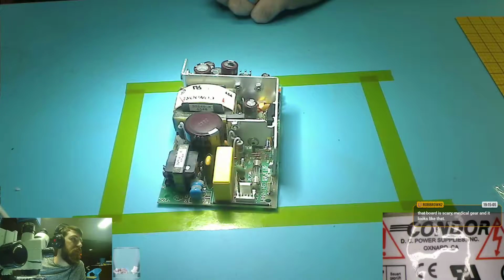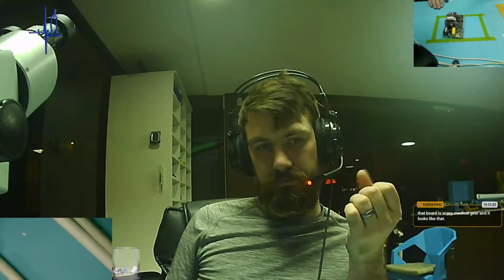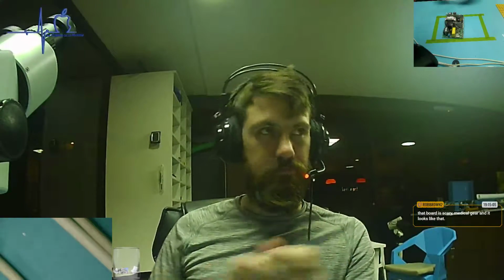Yeah, I know. It is scary. Luckily, I guess that is the failing proof to this piece of equipment. It's actually a fairly new-ish piece of equipment, 2016, I think. But when they fail, and this is kind of a standard with all medical equipment, they fail in a safe method. Big selfie cam, there we go. They fail in a method that's designed to minimize damage and the possibility of hurting a patient.